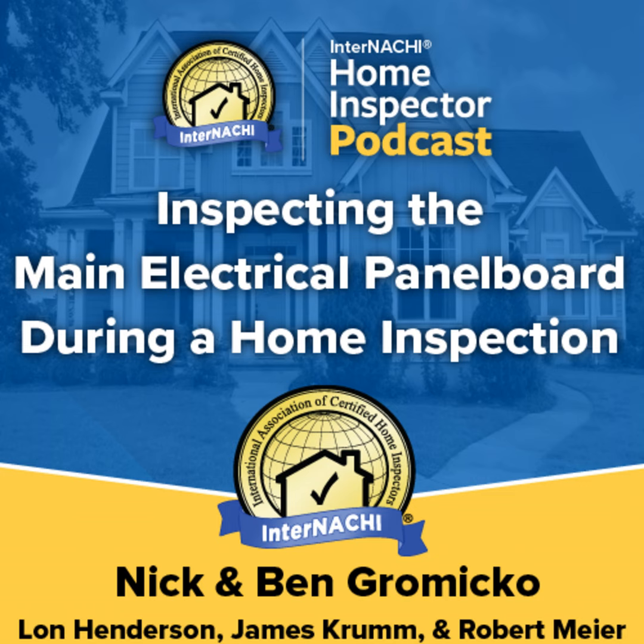Electric service. Electric service is a general term used to refer to all electric service conductors and equipment. The service begins at the load end of the service drop or lateral and ends at the panel board cabinet that houses the main disconnecting means. Power from the utility company is typically delivered through 3 large conductors, which may enter the house overhead or underground. Overhead service wires are called the service drop. The service drop runs to a weatherhead at the top of a length of rigid conduit called the service mast. A typical 3-wire service drop consists of 2 insulated hot conductors wrapped around a bare, stranded aluminum wire with an internal steel messenger cable. The bare aluminum wire also serves as a neutral.